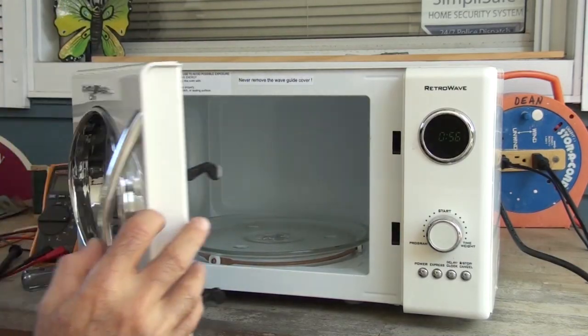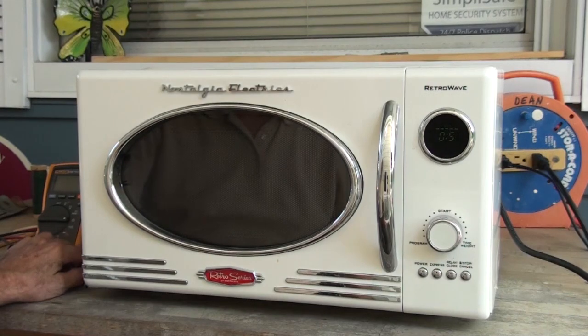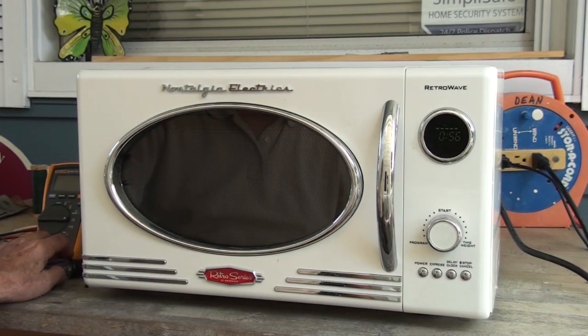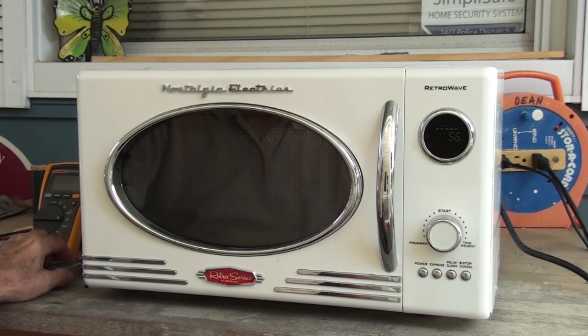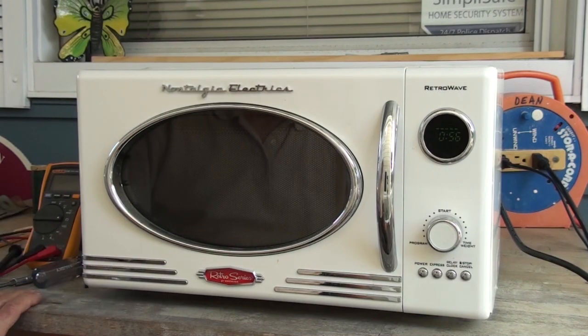So, what clues does this give us? Well, first of all, we know the main fuse isn't broken because everything except the heating works. And we know that the door switches seem to be working okay because they energize. That loud hum obviously comes from the main power supply for the Magnetron that's in there. So we know that the door switches are working, allowing the power to get to the heating part of the microwave oven. So we're going to go inside and investigate what could be wrong other than what we just mentioned.